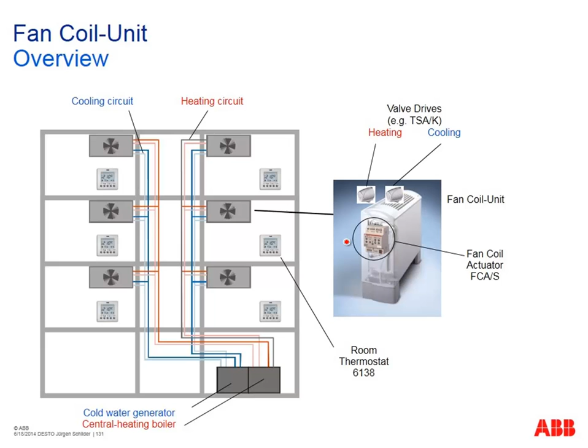The fan coil actuator is connected to KNX and communicates via our KNX room thermostat, for example here the 6138. Depending on the current temperature and the set point, the room thermostat sends the control value to the fan coil actuator. Additionally, the room thermostat is listening to the magnetic reed contact, and when the hotel guest opens the window, it sends the control value 0, closes the valve drives and stops the fan. Or, listening to a time switch or a keycard reader, it changes the mode from comfort mode to standby mode and sends different control values to our fan coil actuator.